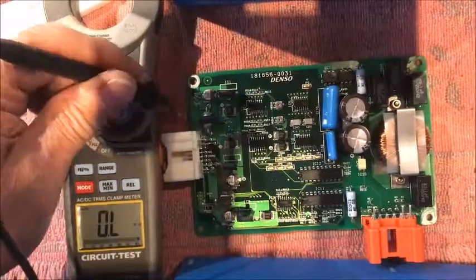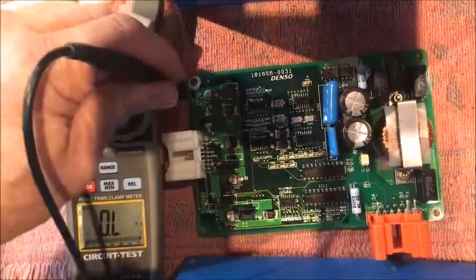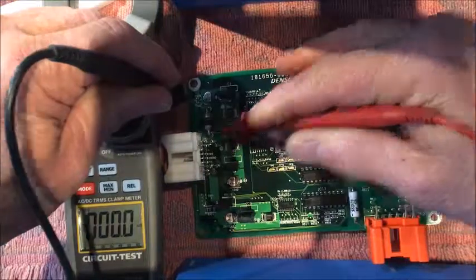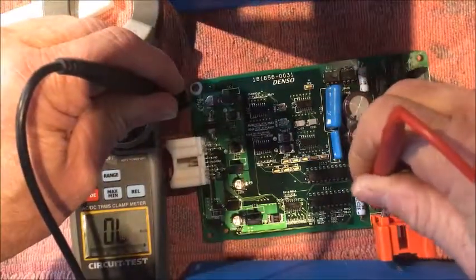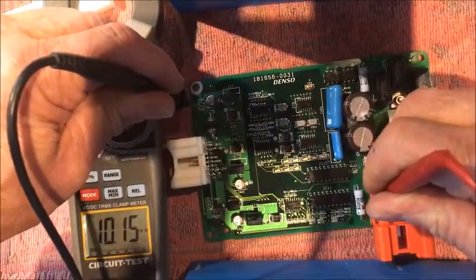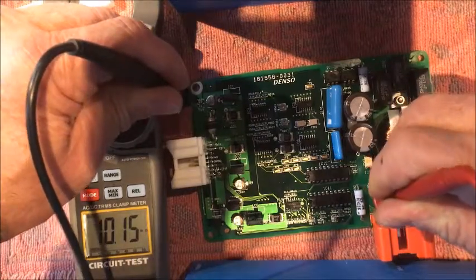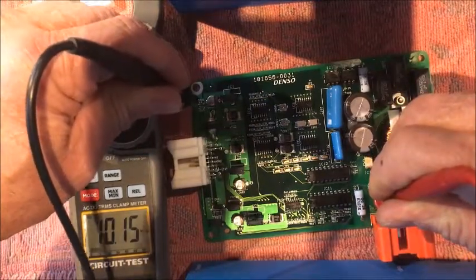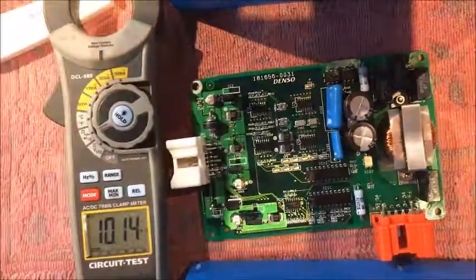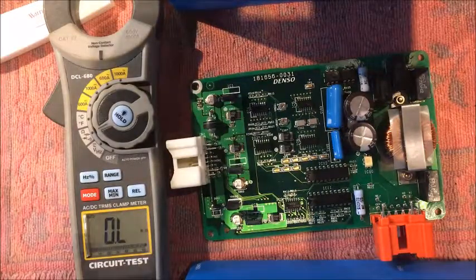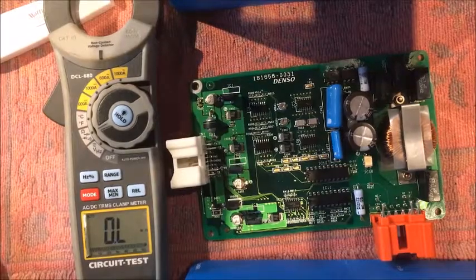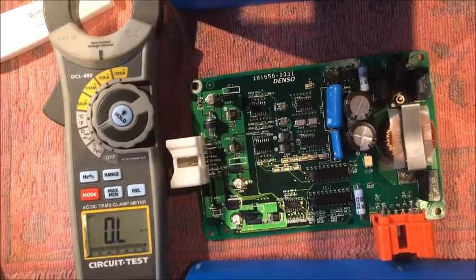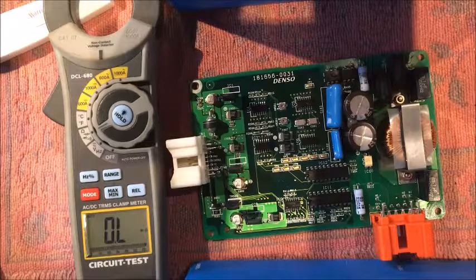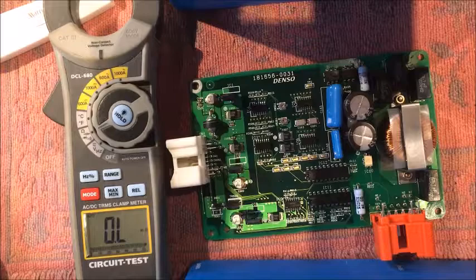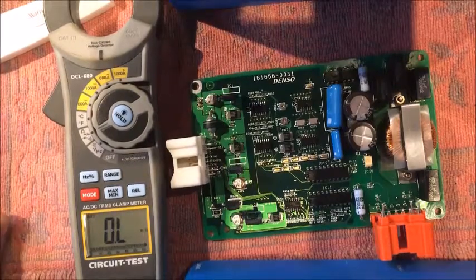So we're going to switch this up now, making sure we've got a good connection on the ground, and back over here to the high voltage ground again, you can see that's 10 megohms. That's about as good as it gets for testing that part of the circuit. If the fault was occurring in that board, you'd maybe get an indication there. But that looks like 10 megohms in one direction, 20 in the other - fairly high impedance using just a regular ohm meter.